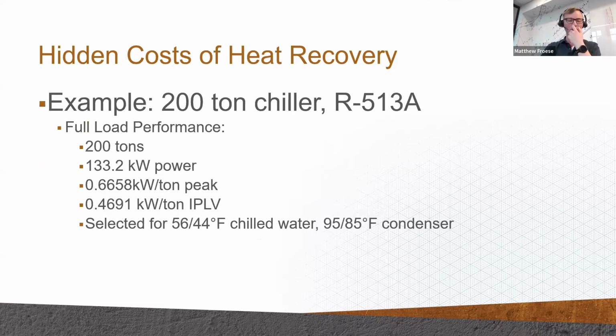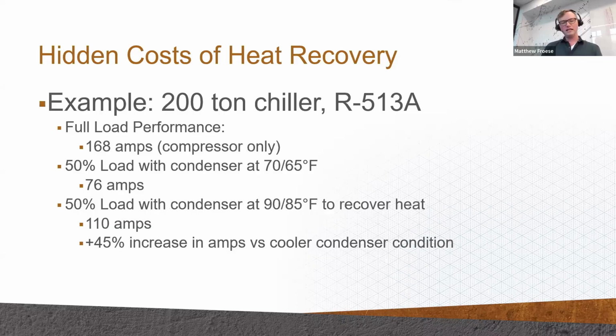So I've got an example here. This is a real piece of equipment that we're working with. Big 200-ton chiller running one of the new refrigerants, R513A. Pretty big. Don't worry about the numbers. But the important thing is, in terms of its loading, at full load, it's going to use 168 amps to run that compressor. But at 50% load, which is where the building's going to run most of the time for most of the systems we ever see, if we can run our condenser loop cooler, if we can reject heat at a cooler temperature, because our load is lower, it's a day that's not super hot outside, the load on that compressor falls substantially. So we see savings beyond just a linear relationship to the load.